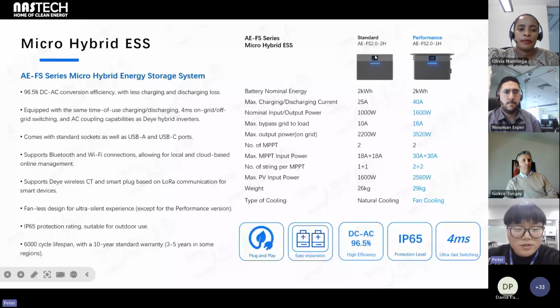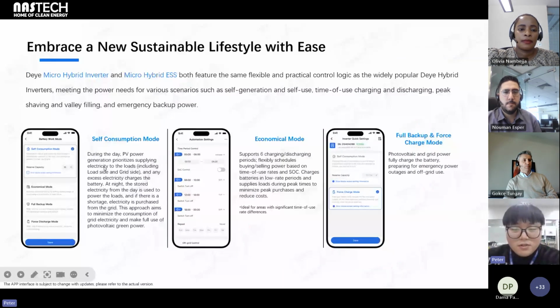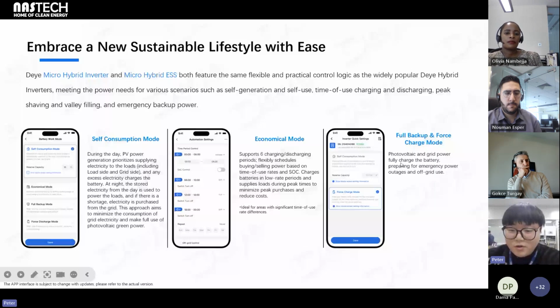On that screen, you can monitor some power flow. And you can use 3 work modes for this product. You can use self-consumption mode, where you save your daily production into the battery and use it at night. In economic mode, you can have 6 different time periods to customize your battery charge and discharge. And in backup mode, you can force charge your battery to 100%, and it will only discharge when the grid is off.